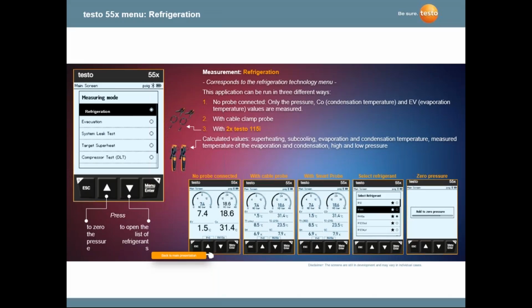If you look at these displays on the bottom, if you look at that center bottom, when I turn on the pipe clamp probes, you're going to start getting your readings from your smart clamp probes. And obviously one smart clamp probe is going to be on the suction line, the other is going to be on the liquid line, and we got the pressures, we got our hoses hooked up to the instrument, blue on the low side, red on the high side, and we're going to start getting our pressure measurements and our temperature measurements and all our calculations. There's over 80 refrigerants that you can select from.